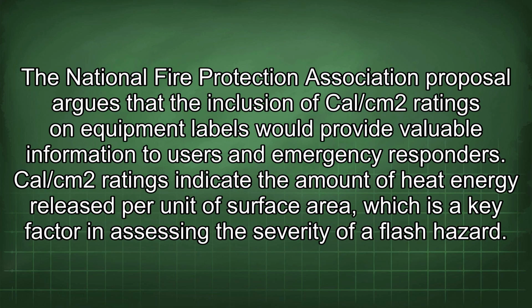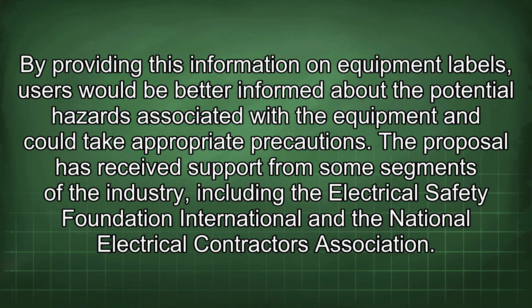The National Fire Protection Association proposal argues that the inclusion of Cal/cm2 ratings on equipment labels would provide valuable information to users and emergency responders. Cal/cm2 ratings indicate the amount of heat energy released per unit of surface area, which is a key factor in assessing the severity of a flash hazard. By providing this information on equipment labels, users would be better informed about the potential hazards associated with the equipment and could take appropriate precautions.